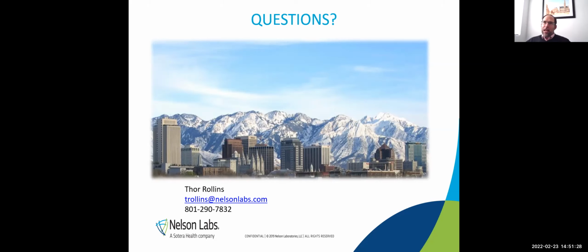So once again, I'm glad whoever asked that question is thinking about processing, because some people would be like, hey, the material's not changing at all. There's no risk. But remember, if we're changing a binder, then that binder, even if it's supposed to be gone, may not be gone. And now we're having residual binder there that we have to be concerned about. What we would do is actually ask for the binder chemical information. And then we would look at that and identify what chemistry technique is the most useful to be able to actually prove that that binder is not on the device.